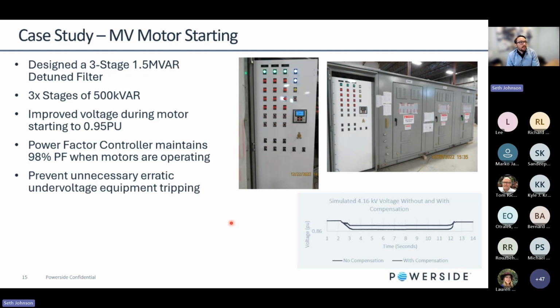I mentioned earlier they needed just under 3 megavar, 3000 kvar of correction to get to unity. We don't need to get to unity power factor during this motor starting sequence. We just need to make sure we're not seeing more than a 5% voltage drop at 5 kV. And honestly speaking, we could have seen a little bit more at 5 kV and been okay, because at the point of common coupling, we're seeing about 2.5 to 3% voltage drop during these motor starting applications.